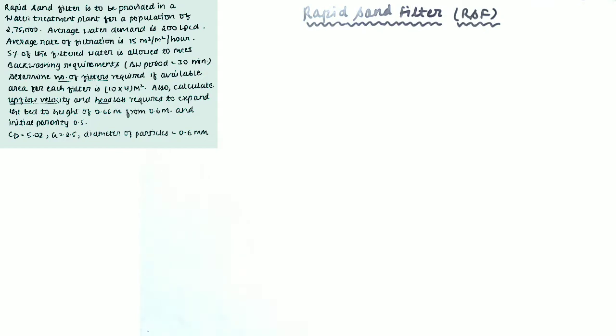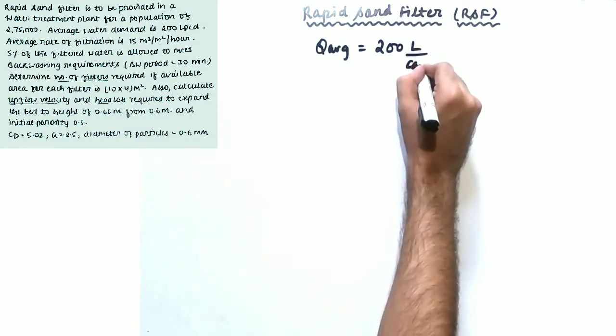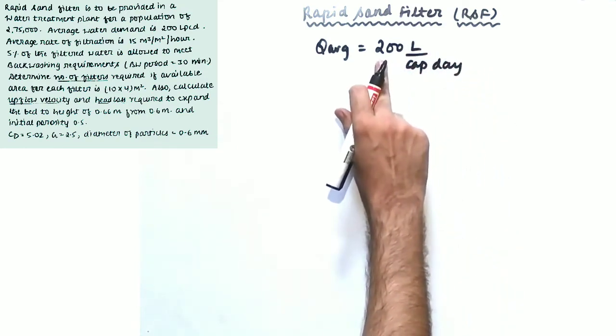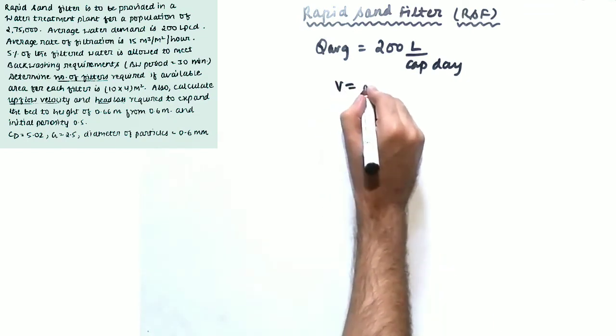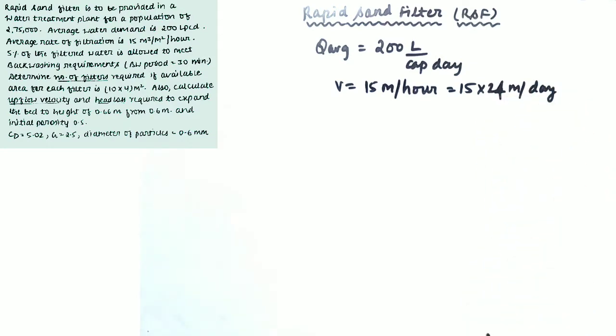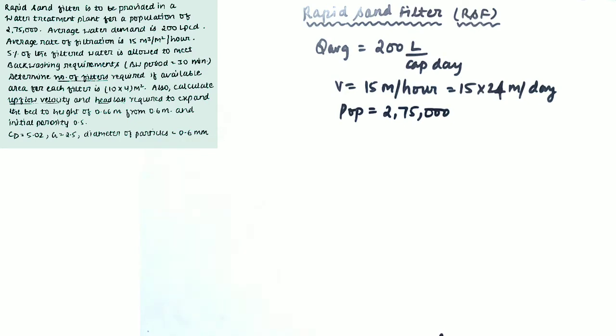In between, I will be telling you the formulas that will be used to solve the questions. The question says that a rapid sand filter is to be provided in a water treatment plant for a population of 2,75,000. Average water demand is given as 200 LPCD — liters per capita per day. That means Q_average is 200 liters per capita per day, meaning one person requires 200 liters per day. The average rate of filtration — that means velocity — is given as 15 meters per hour, which we can convert to meters per day by multiplying by 24. And 5% water is used in backwashing.